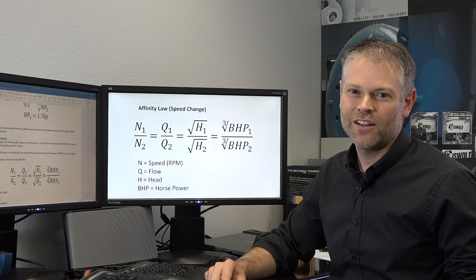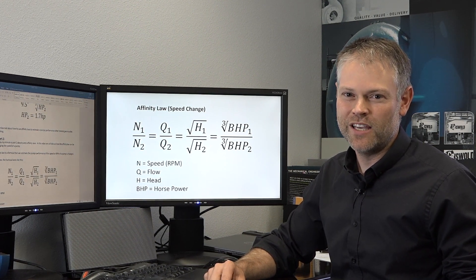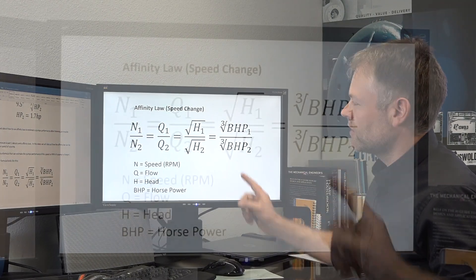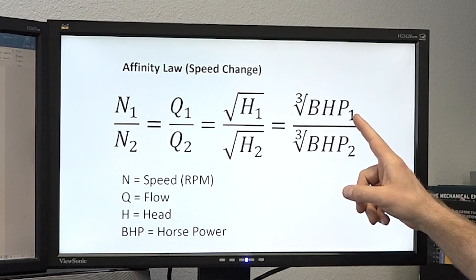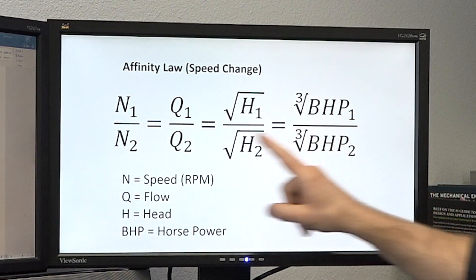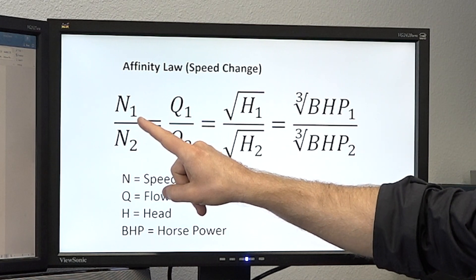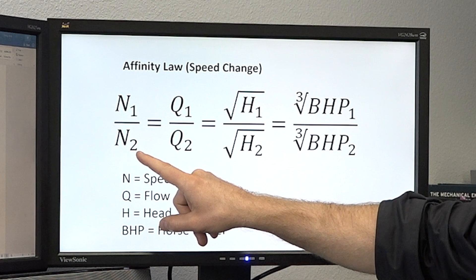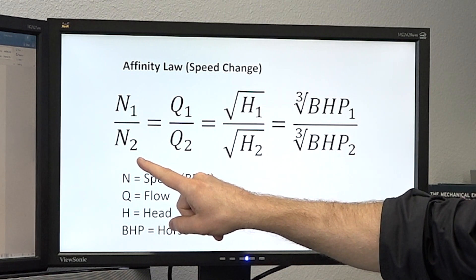The affinity law is a formula that can be used to predict pump performance when you change speed. And this is the equation. It has four elements: speed, flow, head, and horsepower. As you notice, the top of the equation has a subscript of one, that is your original pump speed. And the bottom of the equation has a subscript of two, that relates to your predicted performance after you change your speed.